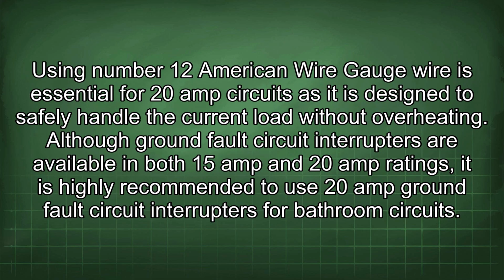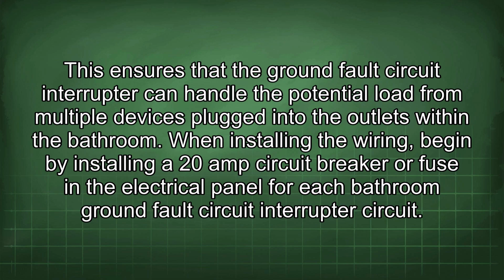Using number 12 American wire gauge wire is essential for 20 amp circuits as it is designed to safely handle the current load without overheating. Although ground fault circuit interrupters are available in both 15 amp and 20 amp ratings, it is highly recommended to use 20 amp ground fault circuit interrupters for bathroom circuits. This ensures that the ground fault circuit interrupter can handle the potential load from multiple devices plugged into the outlets within the bathroom.